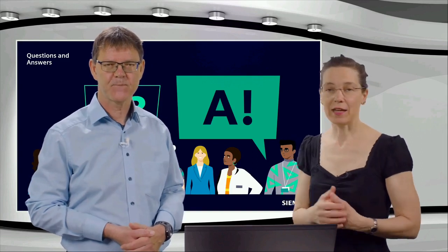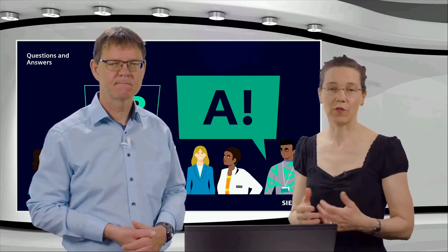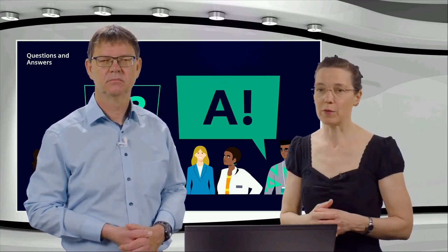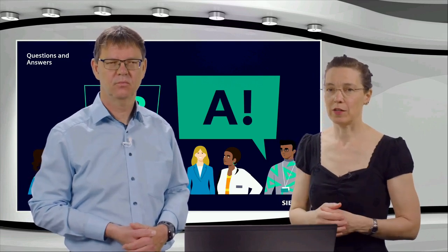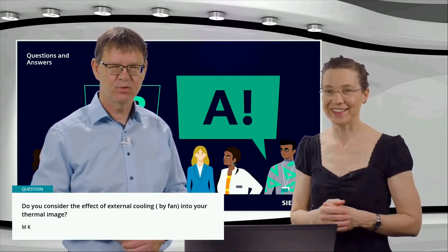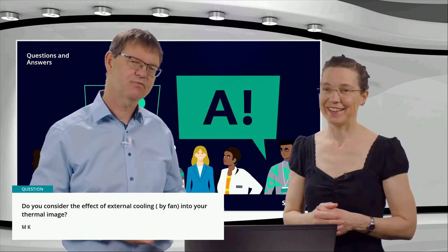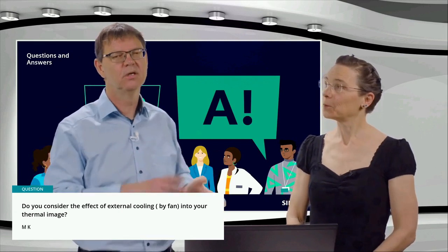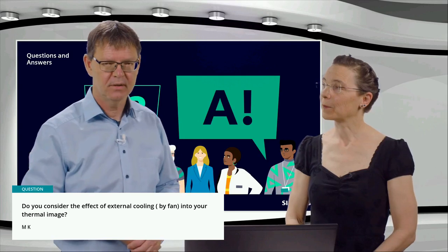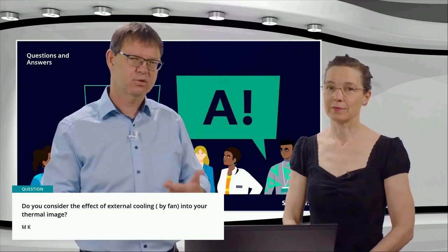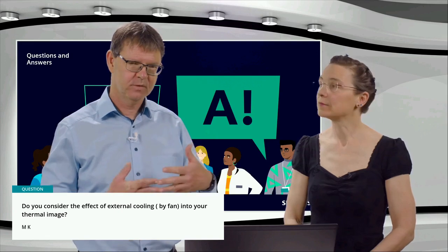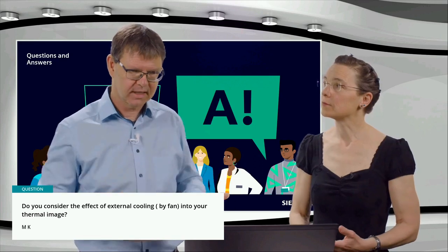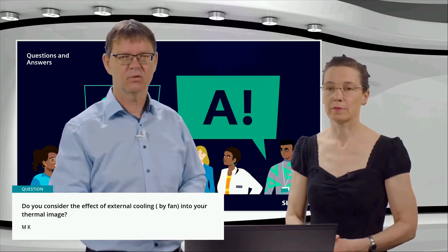Then MK has a question about the thermal model we have of the motor. Do you consider the effect of an external cooling, for example with a fan, in the thermal image? Yes, this we do. We have different time constants for the running and for the standstill motor, for the stator temperature and also for the rotor temperature. In the stator overload protection, we have two settings, two time constants, and with that we can consider that.